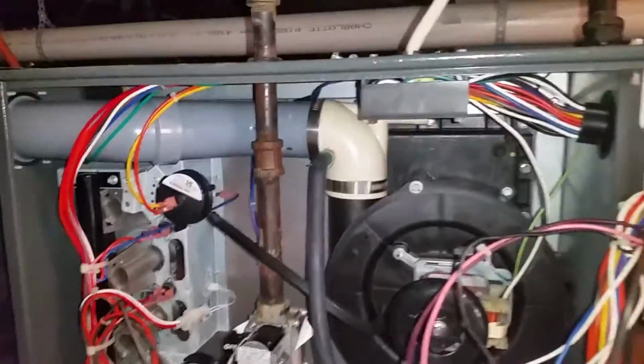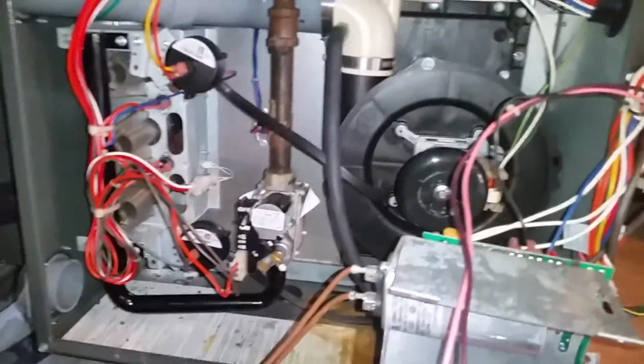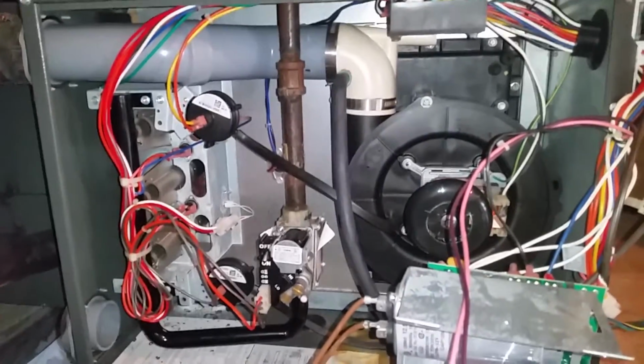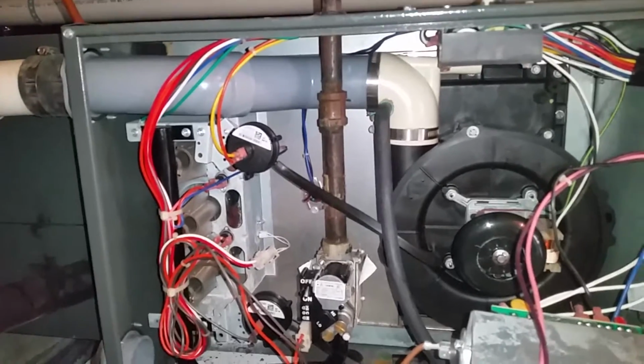So we're going to look at the condenser coil side, and there is some right here, and a little bit, as you can see, the staining right there, where it looks like it's come through, but that's not the main telltale on this one. We're going to see on the inside, it's got a lot of acidic corrosion on the inside of the heat exchanger. So I'll open it up some and show you that.